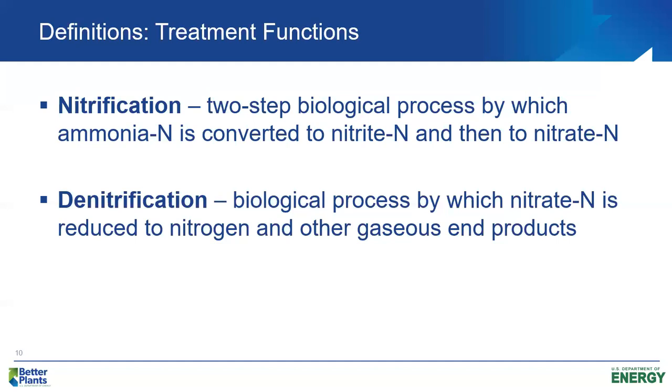Now, denitrification is biological nitrogen removal. Under anoxic conditions, we take away the oxygen so the bacteria don't operate in the aerobic mode, and then they look for their next preferred electron acceptor, and they'll look for nitrate, and nitrate is present in the absence of oxygen. They'll use nitrate as their electron acceptor, and they'll operate in the anoxic mode. They'll strip the oxygen off of the nitrate and produce nitrogen gas.